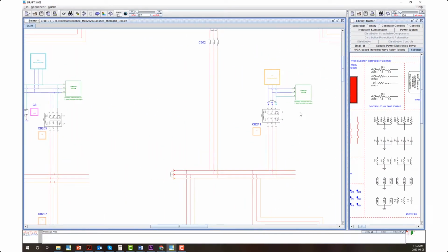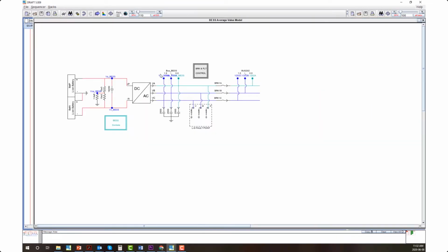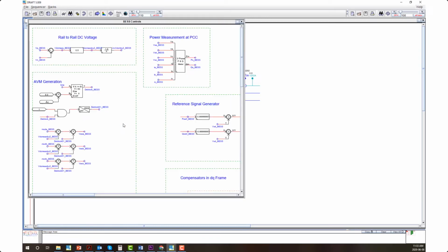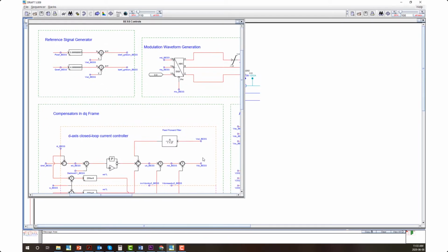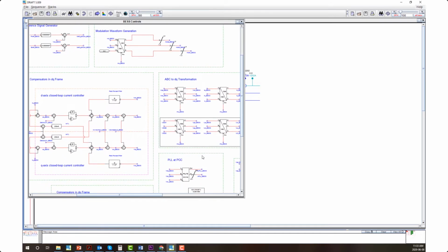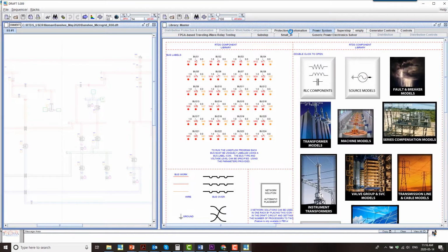However, this level of resolution is not always necessary when testing higher-level microgrid controls or system dynamics. RSCAD also contains average value models, which run at the main simulation time step. These models accurately represent the steady state and transient behavior of the converter without representing the high-frequency switching dynamics. In situations like this one, where many converters must be modeled without requiring the testing of low-level control, average models are often used to reduce the amount of simulation hardware required.